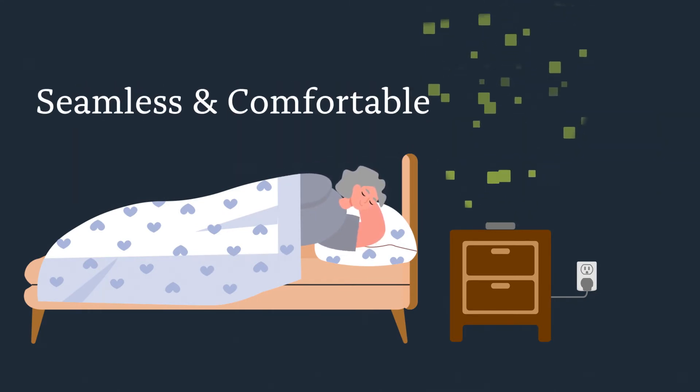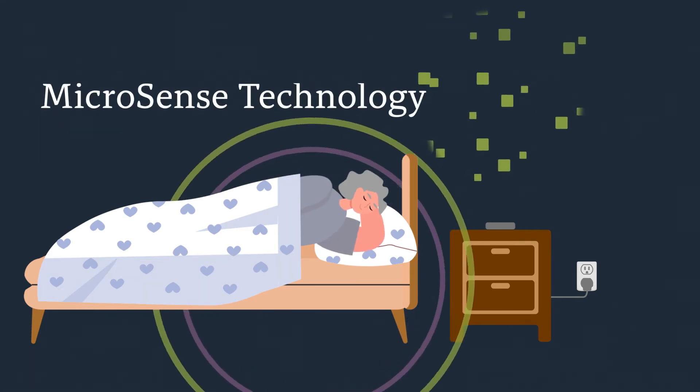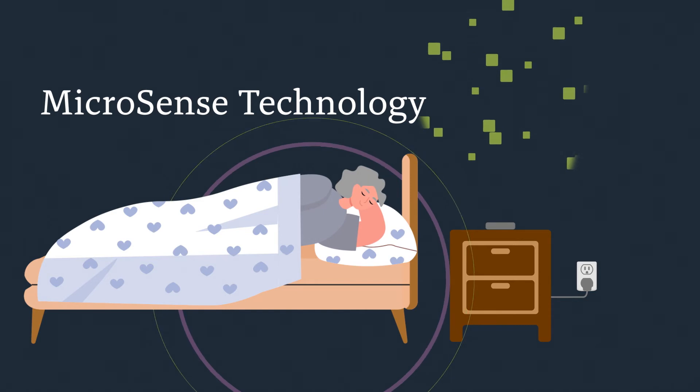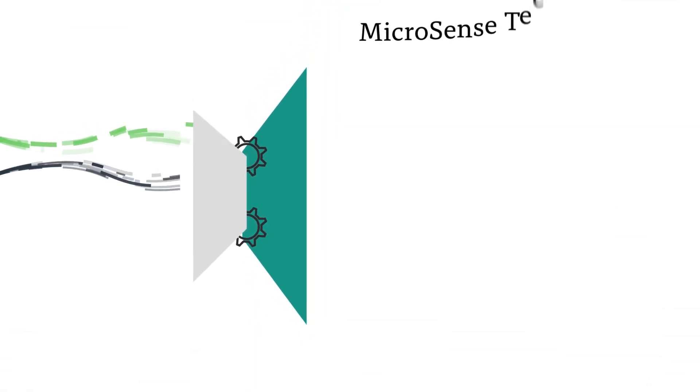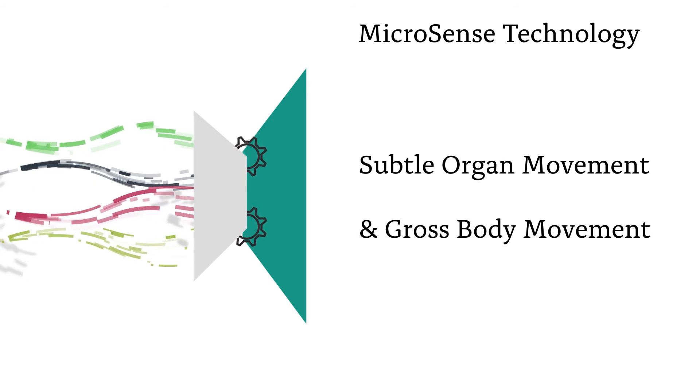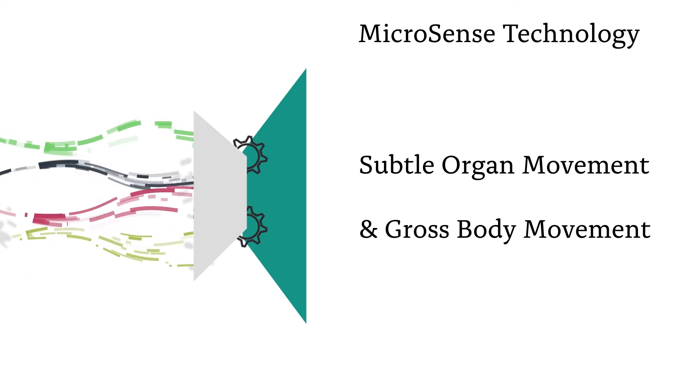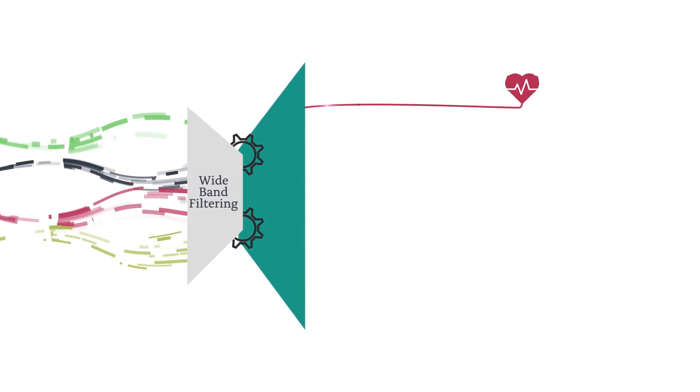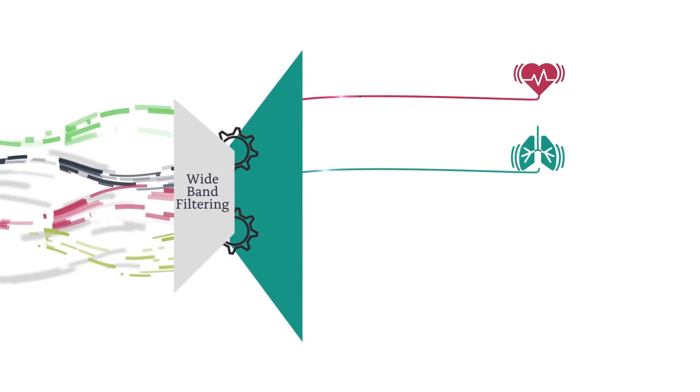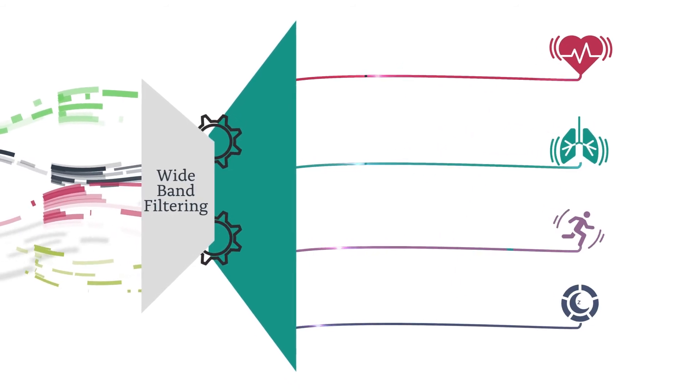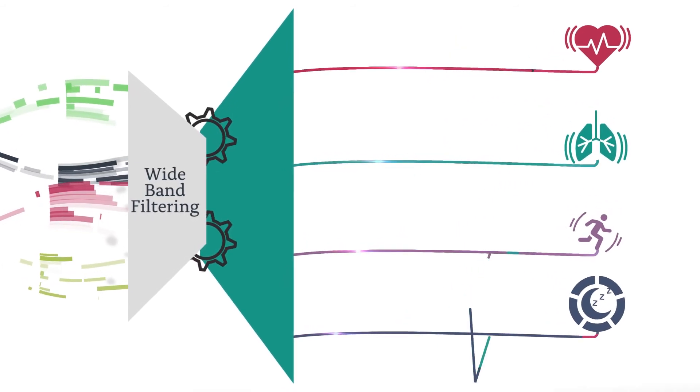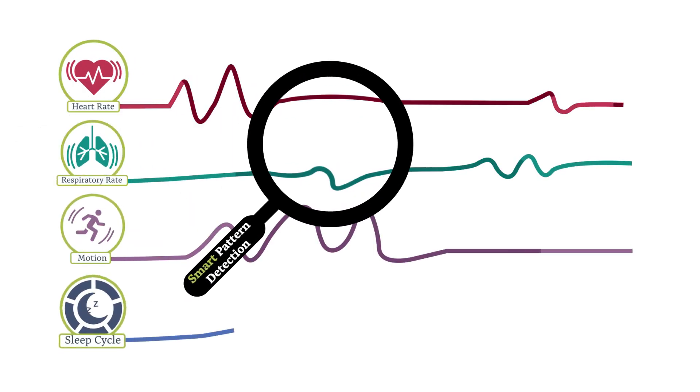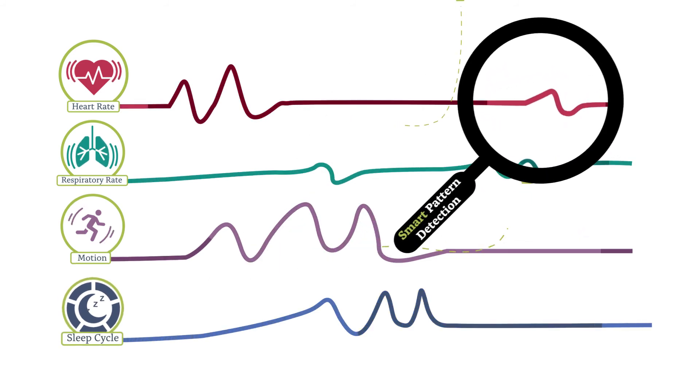Seamless and easy to scale integration. The sensor is specifically designed for use in remote and virtual monitoring settings. And uses adaptive algorithms to capture and analyze both subtle, small organ movements and large gross body movement simultaneously. Wideband filtering analyzes signal pattern changes and automatically detects when an individual is awake or asleep. Filtering out clinically irrelevant data like a partner in bed. Using smart pattern detection, the system learns and adapts to an individual's unique signals and patterns day over day as they're monitored.